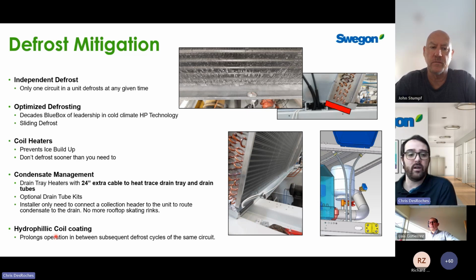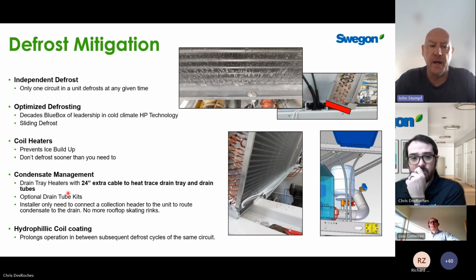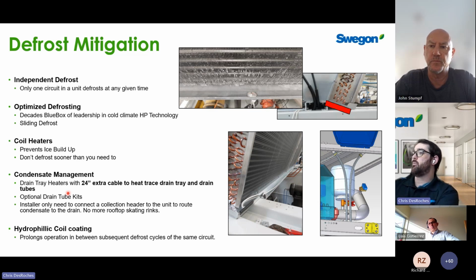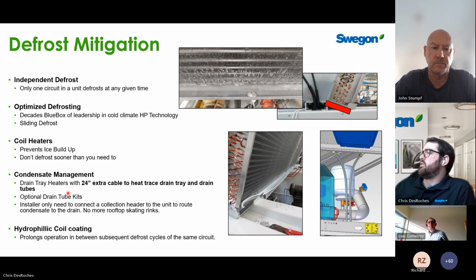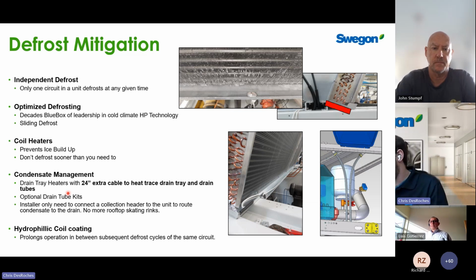We had done testing. Yeah. Hey, this is John. So with this coil coating, does that extend the defrost times from like say 60 above to longer numbers like 90, or what do you think? Yeah, so that's what I was getting at. In the lab, we had done testing where with standard fin tube, we defrost once an hour. With the hydrophilic coating, we defrost once every hour and a half. So we're spending much longer time in between subsequent cycles. So a lot of thought has gone into this.